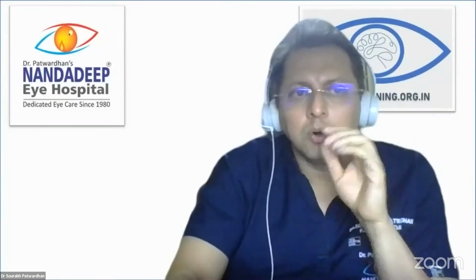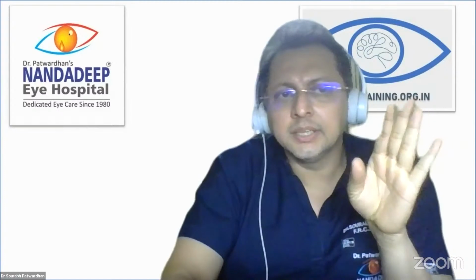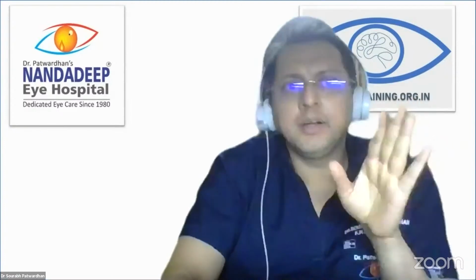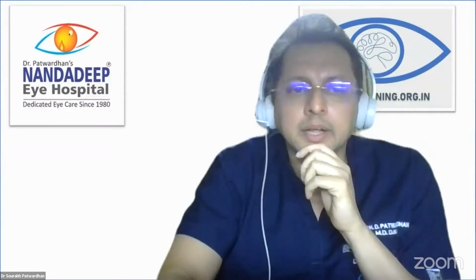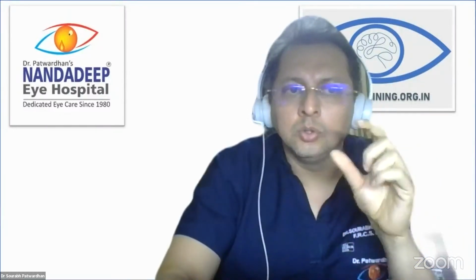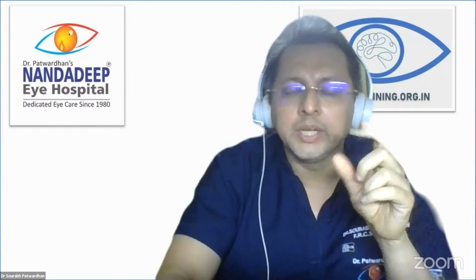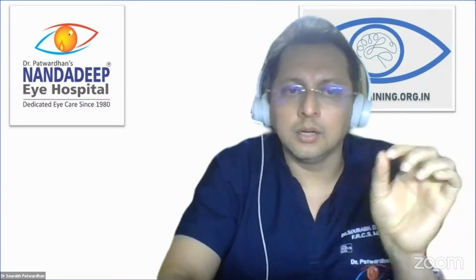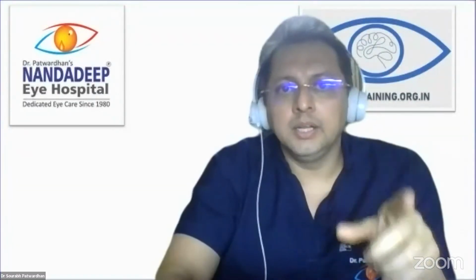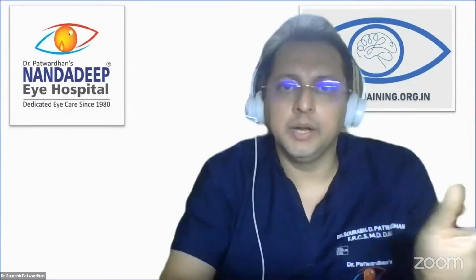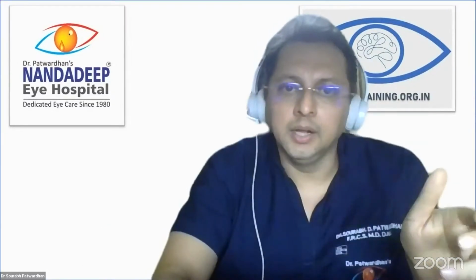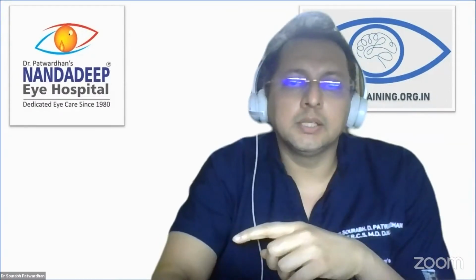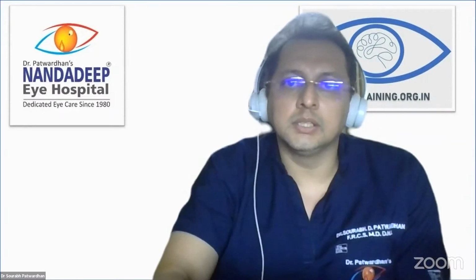Filter validation has to be done on a regular basis. OT validation is provided for 6 months only, so after every 6 months you have to get it validated again. Though we cannot clean the HEPA filter, there are outer filters, which are large bore filters that catch basically the bigger particles. So it's better to clean them weekly or every 2 weeks, depending on how much OT you are running. That will reduce the chances of HEPA filters getting blocked if you clean those filters regularly.